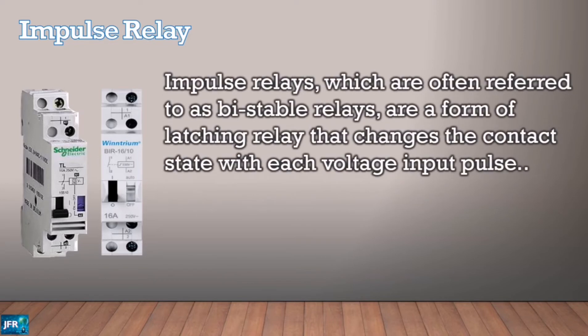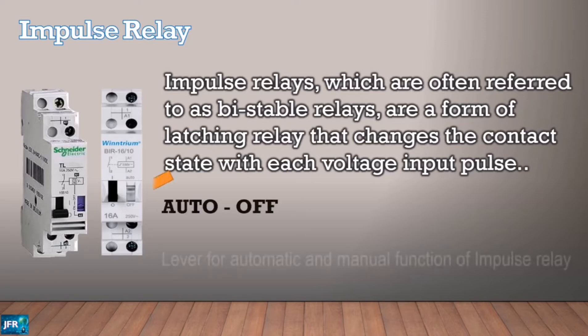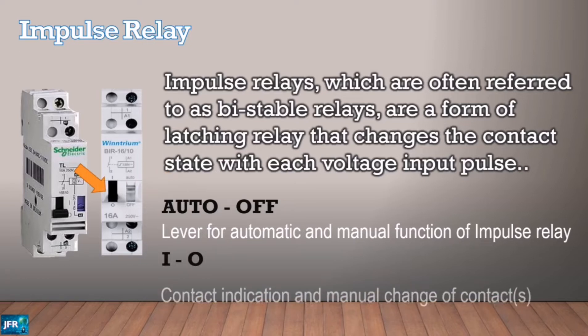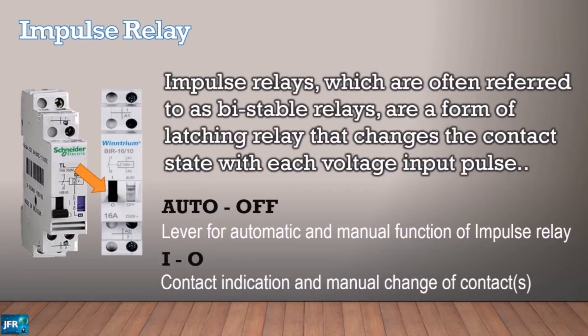Impulse relays, which are often referred to as bi-stable relays, are a form of latching relay that changes the contact state with each voltage input pulse. It has two lever switches: one is the auto-off, which is used to change the impulse relay function between auto and off. The other is the IO lever switch, which is a contact indicator and also used to manually change contact status.